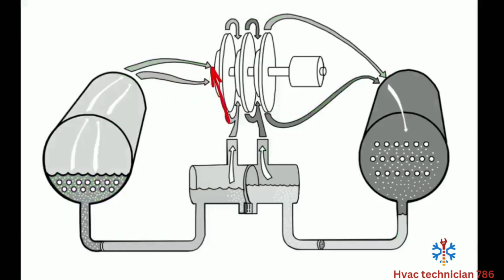And this is the same schematic, but for a CVHE or G series. Your first stage IGV here, going into your first stage impeller. You'd have a fixed guide vane for your second stage, and that would flow into a variable guide vane for your third stage, and then out your discharge line into your condenser. Just to give you another depiction of what it looks like between a CVHE and F series.